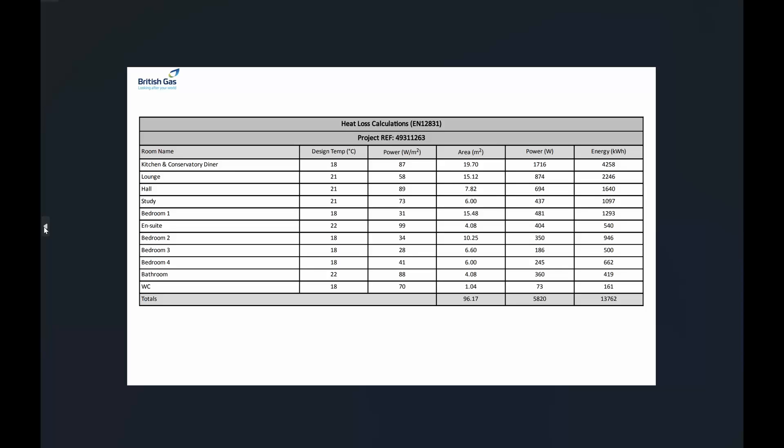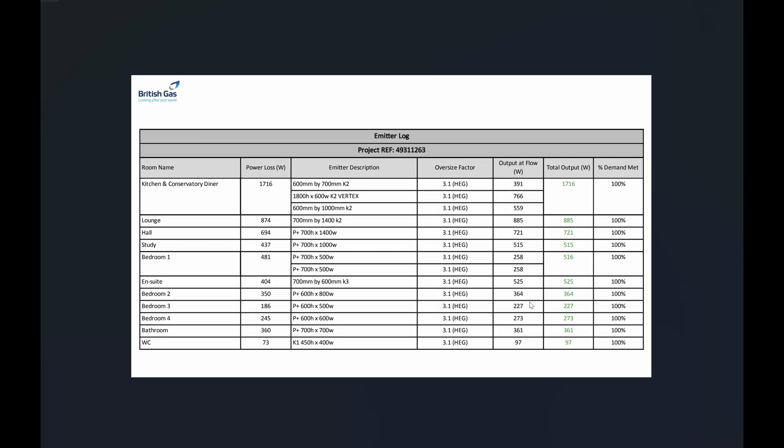Starting with a full heat loss calculation. Here you can see the design temperature for the different rooms, watts per meter squared required, the area of that zone, and then the actual power in watts and the energy needed in kilowatt hours. So my total heat loss for the spaces that we were going to be heating is 5.8 kilowatts. Now we do have some spaces that previously were heated and they do have radiators in and they are still connected onto the heat pump circuit, but they're storage unheated areas really for most of the time.